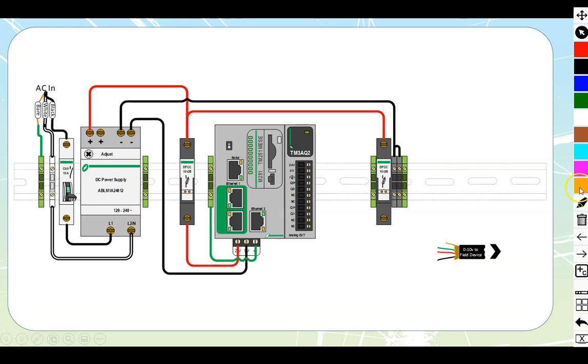Okay, let's apply that wiring. Let's start by doing some grounding and bonding. We're going to take this shield and apply it into our ground. We're going to take our ground for this cable as well, which is different than the shield. The shield drains off charge and prevents electromagnetic induction. The ground is the ground that actually runs inside of the cable itself. Both of them go into this ground. And while we're dealing with grounding and bonding, we're also going to pick up the ground on the card itself.